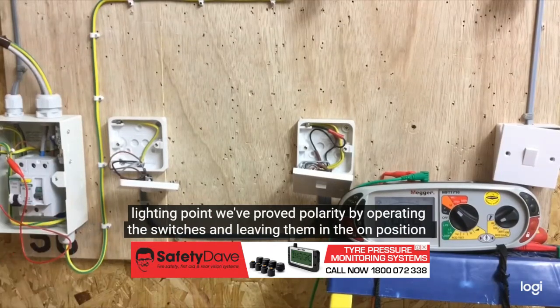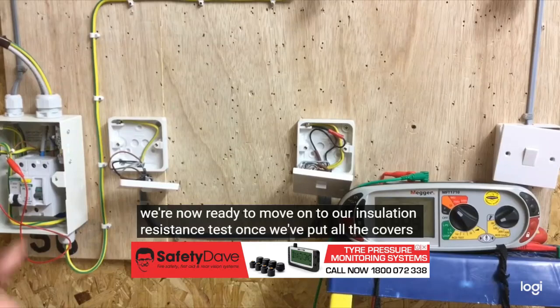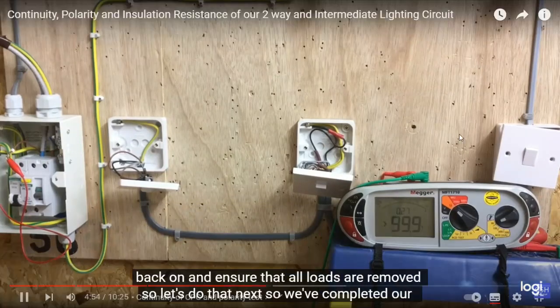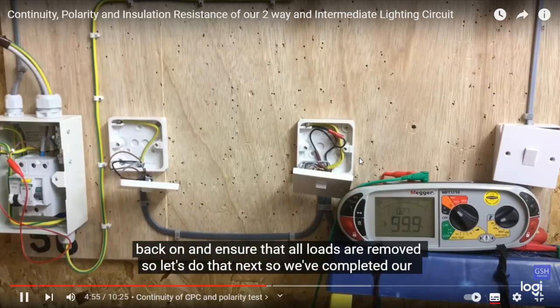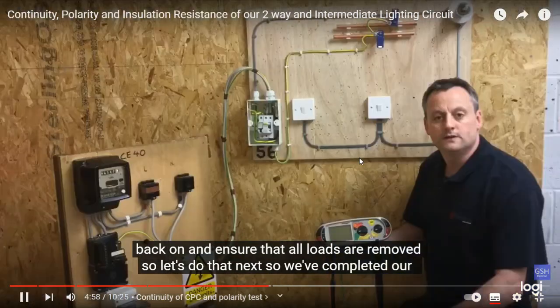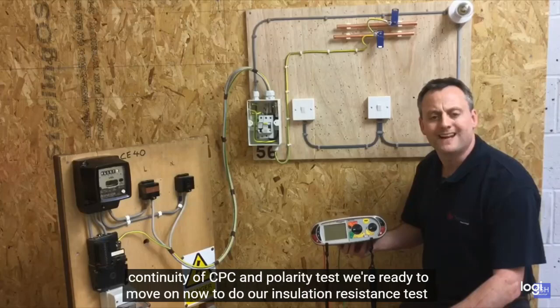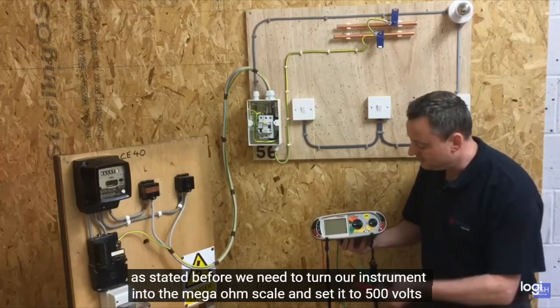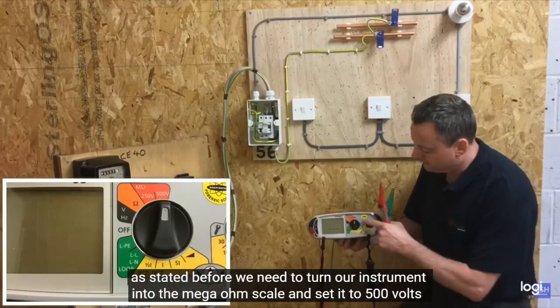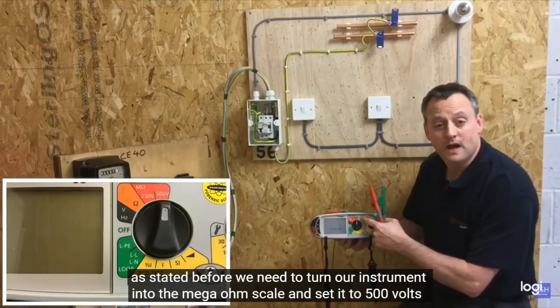So we've completed the continuity of CPC and polarity tests. We're ready to move on now to our insulation resistance test. As stated before, we need to turn our instrument to the megohm scale and set it to 500 volts DC. We've also inserted, as before, our leads into the green and red sections of our MFT. Once again, we could have used the blue lead, but we've chosen to use the red and green leads.